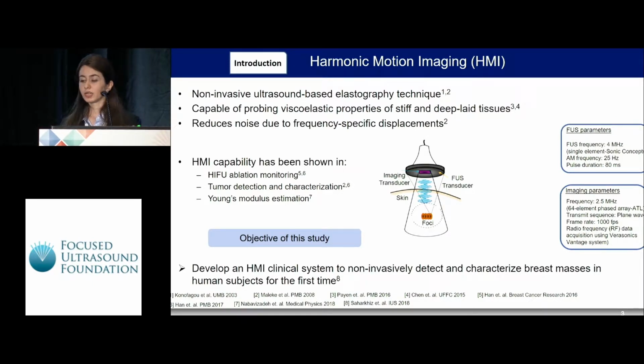Harmonic Motion Imaging, or HMI, is a non-invasive ultrasound-based elastography technique, which consists of 2 confocal transducers. The focused transducer generates amplitude-modulated acoustic radiation force within the focal spot, and the resultant displacement is tracked with an imaging transducer. HMI is capable of probing viscoelastic properties of stiff and deep-laid tissues, and since the displacements are at a specific frequency, it allows noise reduction in displacement estimation.